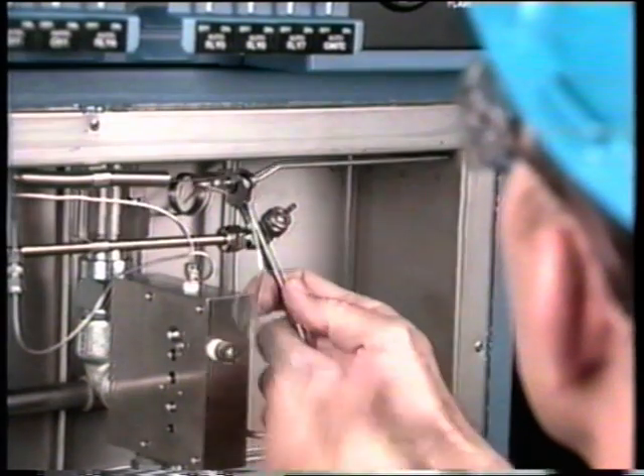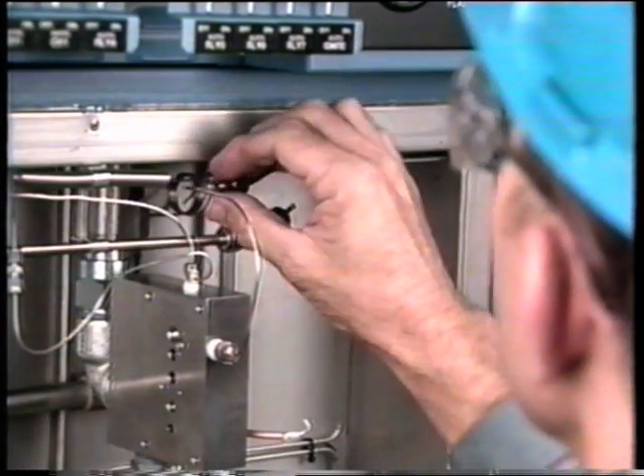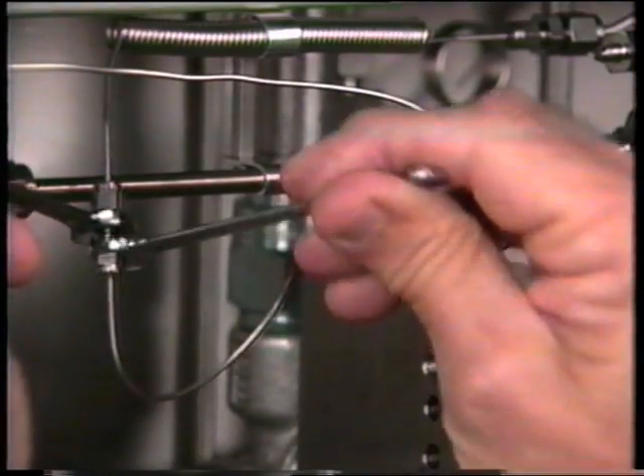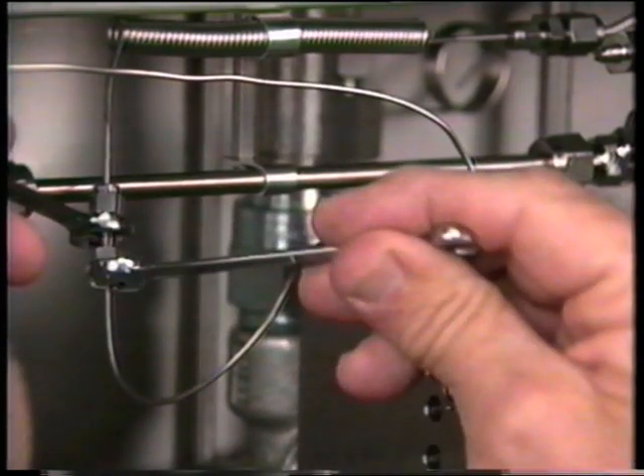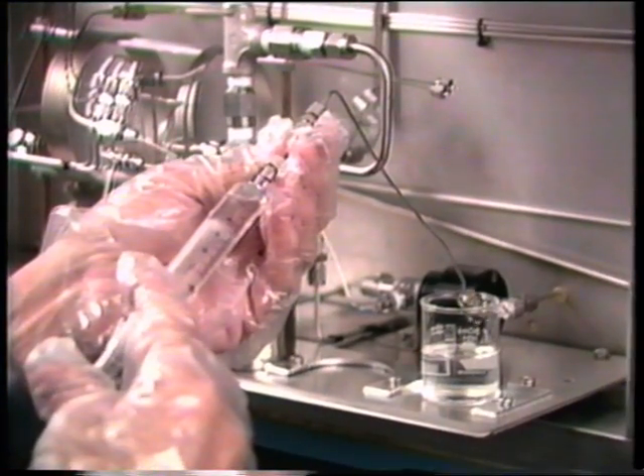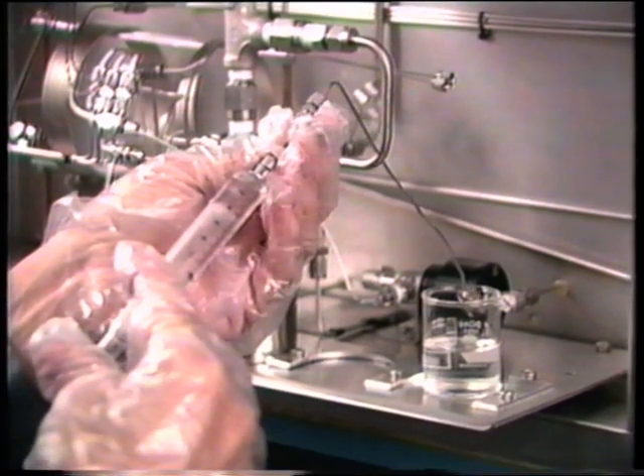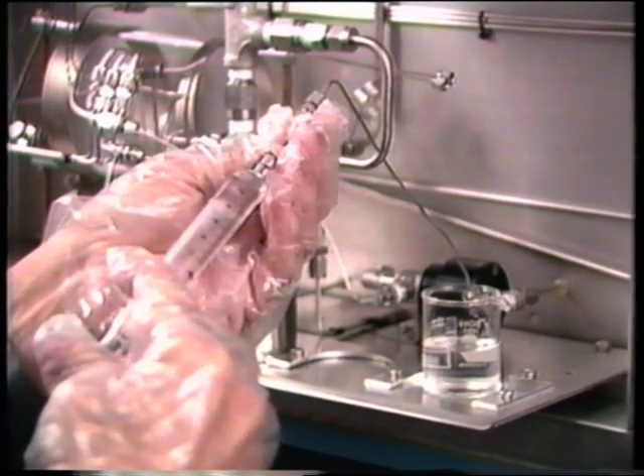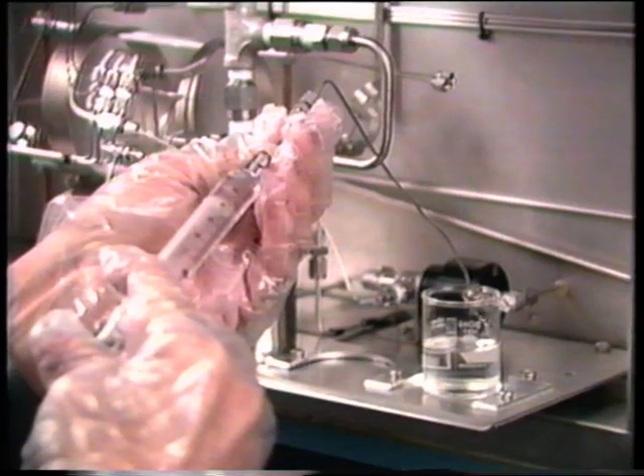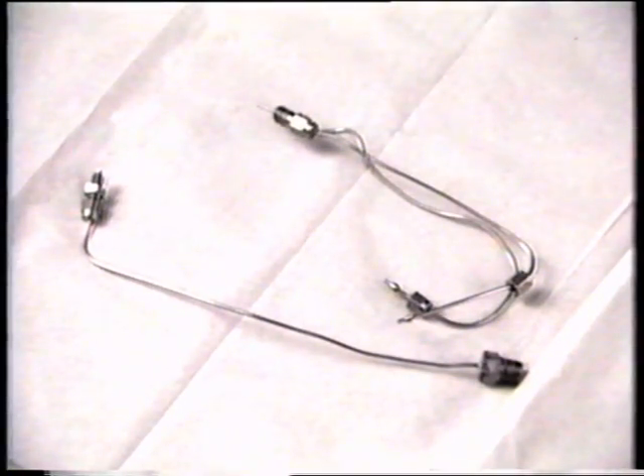Disconnect and remove the air supply line from the body of the unit. Remove column effluent and hydrogen supply lines. Flush these lines with a solvent by forcing the fluid through them. These are capillary lines and have a low flow rate. Set the lines aside to air dry. Replace any worn or damaged parts.